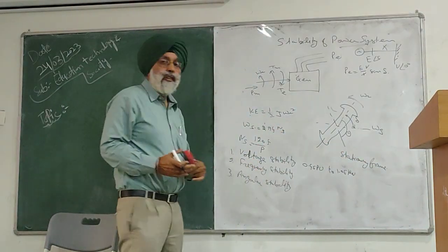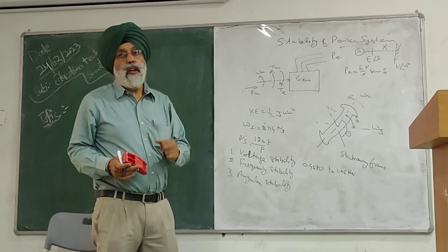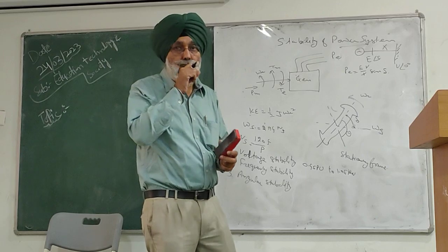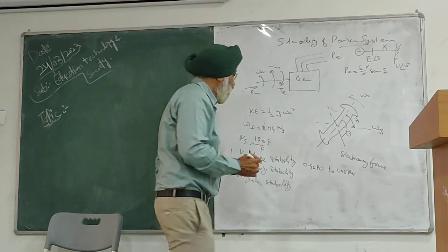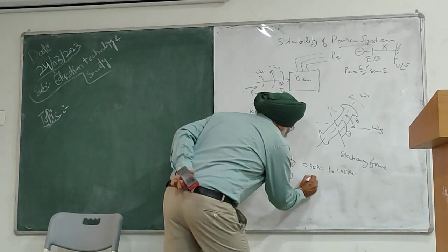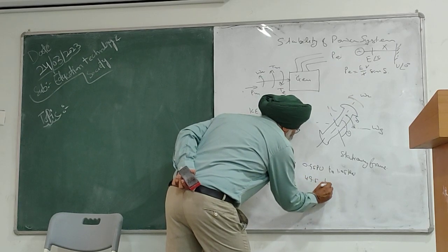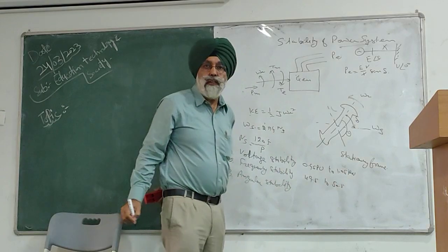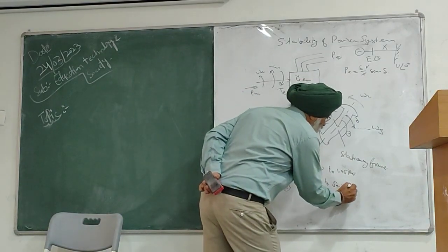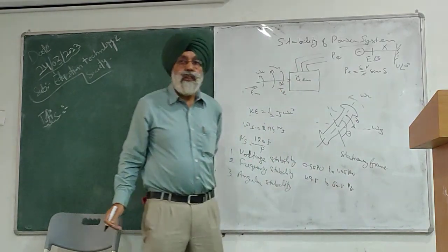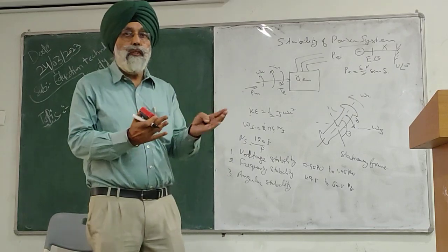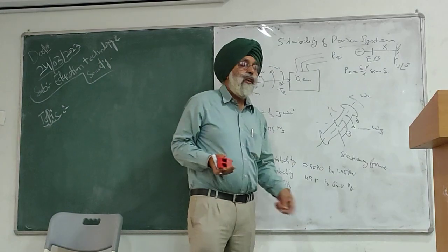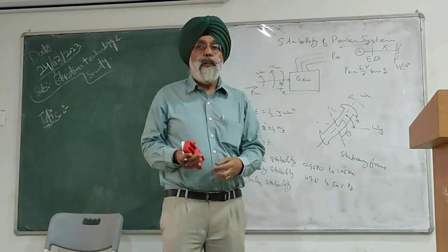So in case of the frequency stability, we allow only 1% variation. So our standard frequency is 50 Hz. So it can be allowed from 49.5 to 50.5 Hz. So this is the variation. Means this is the tolerable limits that your system can work at, 49.5 or 50.5.